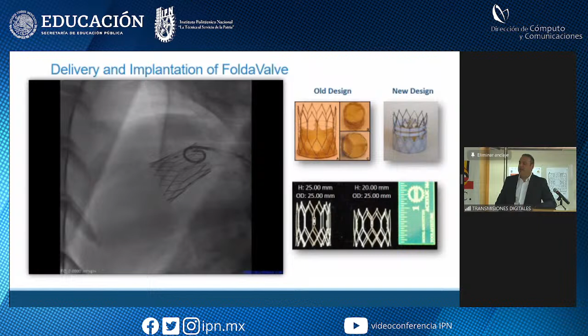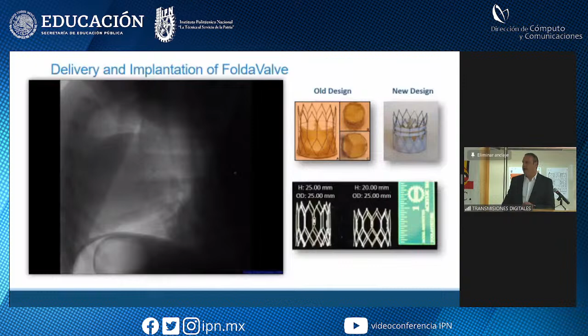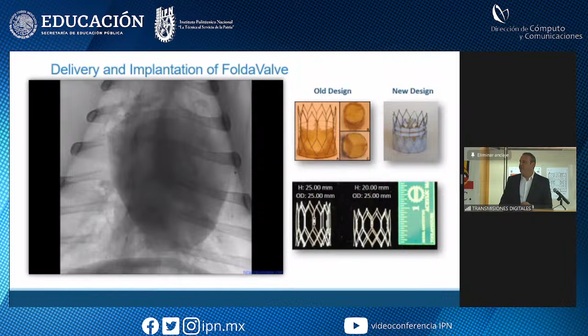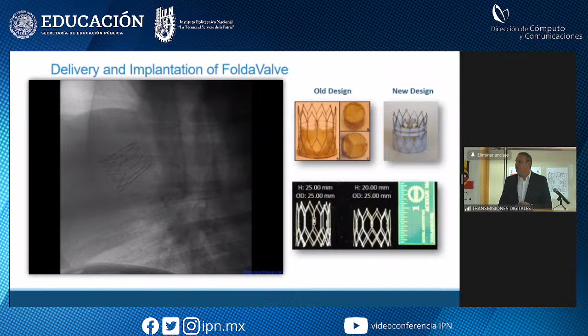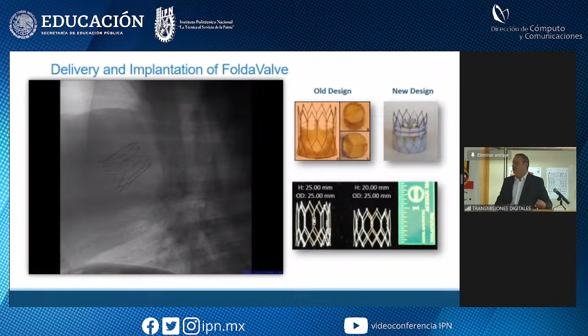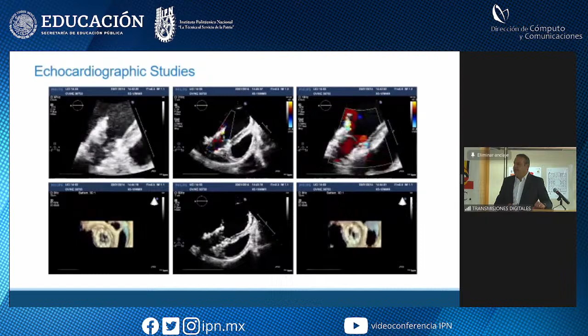This shows the sizing after we implanted, and everything is as planned. This is again fluoroscopy, in the sheep heart. Obviously there are two designs, and we learn a lot of information through our animal studies; for example, the newer design is a little bit shorter than the older design. If you go to the next slide, please. These are the echocardiographic studies. We want to make sure the valve is working perfectly when it's implanted in the animal. Next slide. More recently, we have even advanced our FoldaValve, and we have incorporated for the first time an intravascular ultrasound technology inside of it.